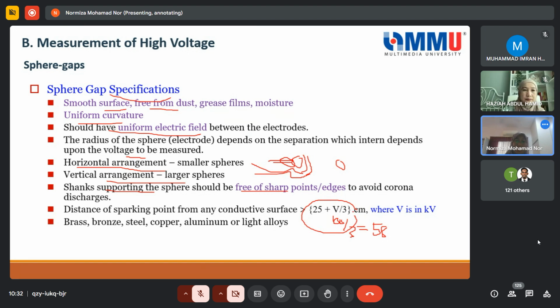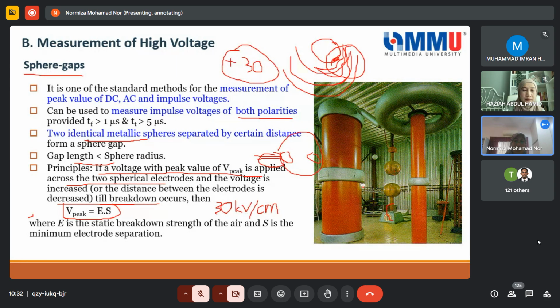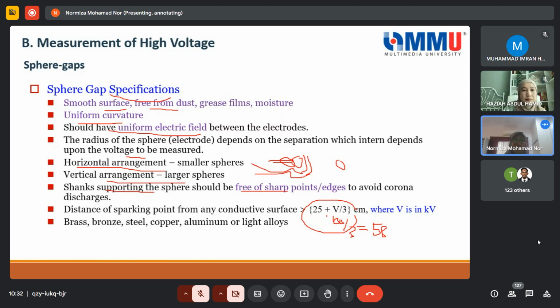It means that, if I go back here, you apply 100 kV from the resonant transformer here. So you should have at least 58, so at least 60 cm from the ground and 60 cm from the surroundings. So it means that you should make a radius of 60 cm from this sphere gap. Sorry, I keep saying spark gap, sphere gap. So that's the condition. So it gives a clearance of 25 plus V over 3.